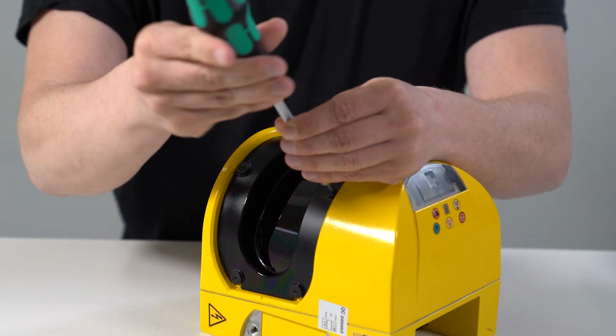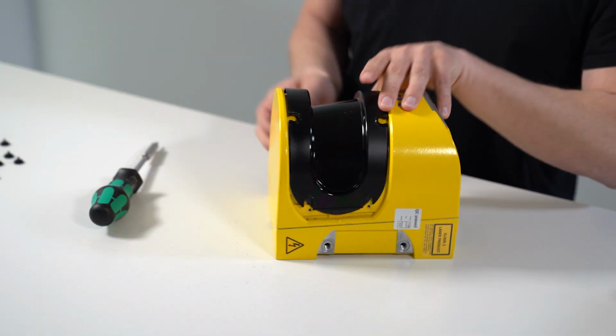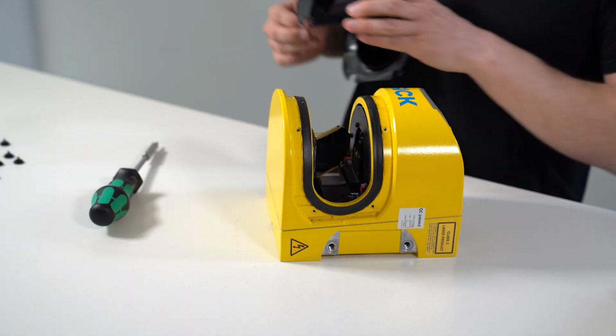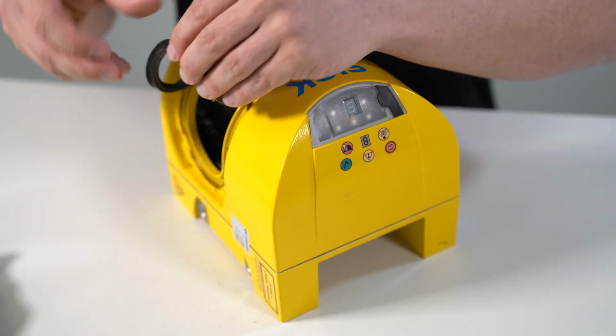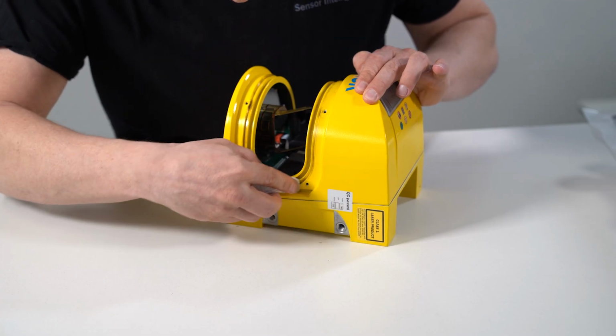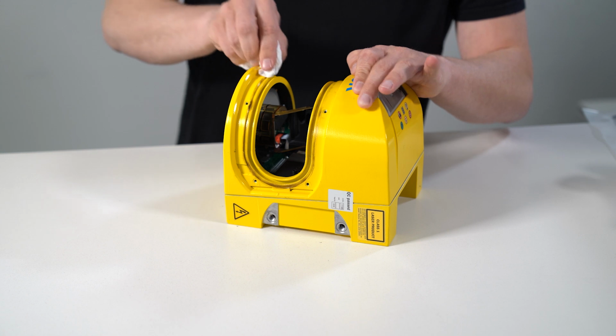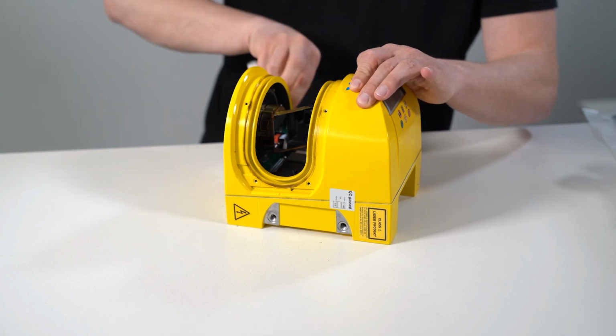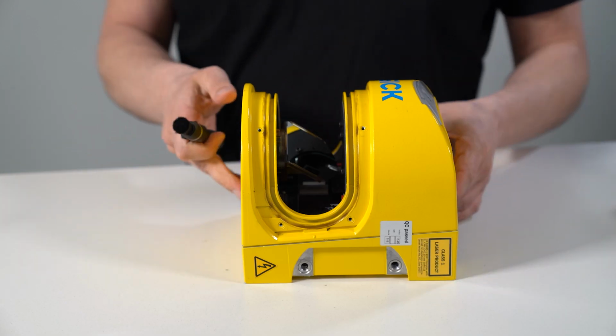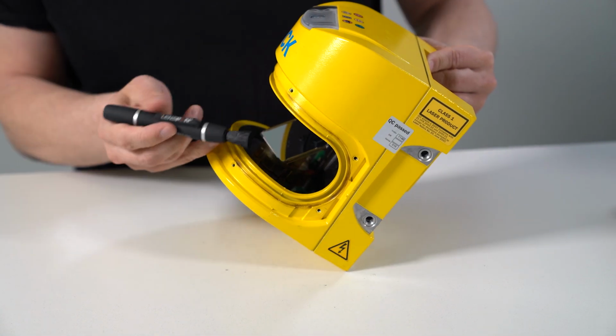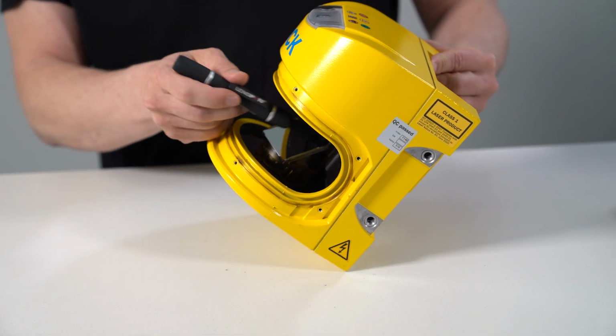Unscrew the screws for the optics cover and slowly and carefully remove the optics cover and the seal from the S3000. If necessary, remove contamination from the sealing groove and the bearing surface of the sensor. Use a residue-free plastic cleaner. Check whether the mirror on the motor is dirty and, if necessary, remove dirt using an optic brush.